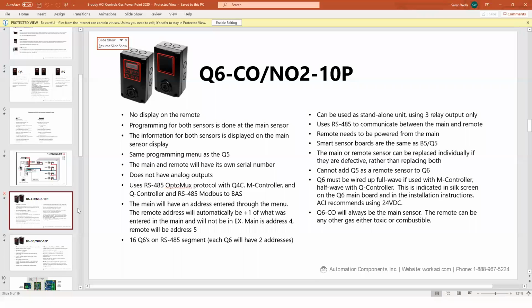These can be used as a standalone system in a small area, like a 1 or 2 car garage, where all they need to do is turn on a fan. You can put the Q6 in there as a standalone - either the CO or NO2 level trips the relay, turns the fan on, and exhausts the space. So for small jobs, the Q6 can be a standalone system, if you're using the relays.